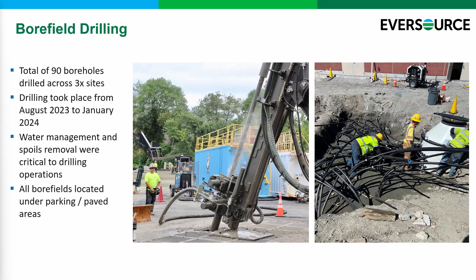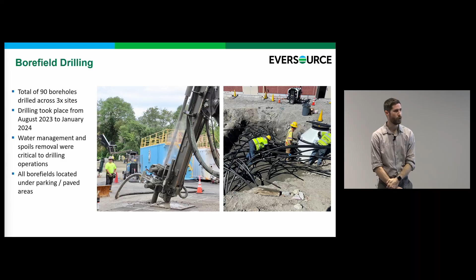Once you've got all those holes in the ground, you have to tie them together with pipes. So you pull all of the inlets and outlets together into a single vault, with a nice long header for each so you can control the individual borehole runs. You can turn them on and off with valves, pressure test them, and make sure the system is running appropriately before you cover it back up. As was mentioned multiple times, you really want to make sure there are no issues or leaks before you backfill these systems.